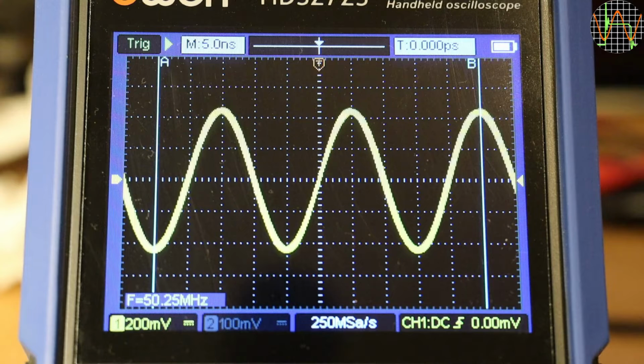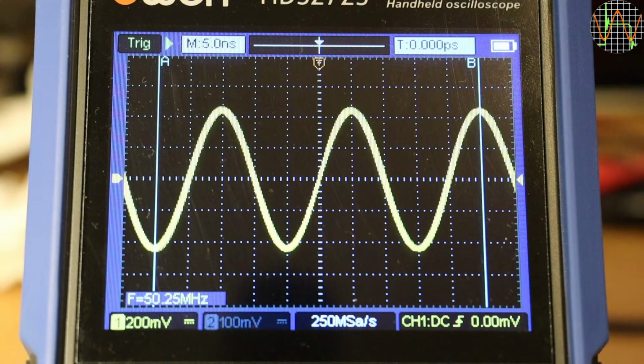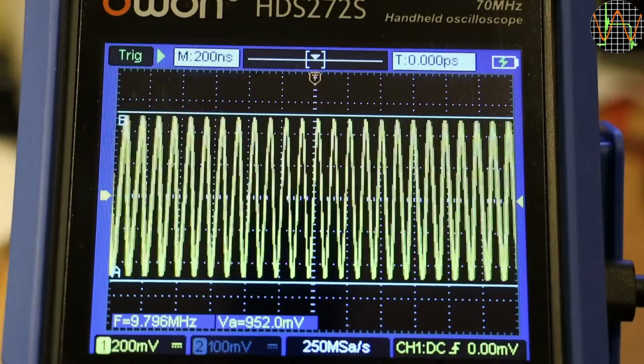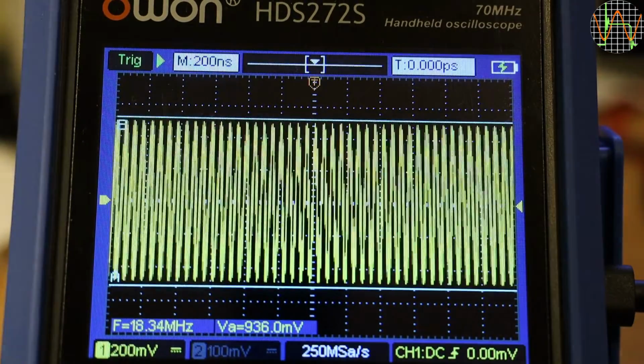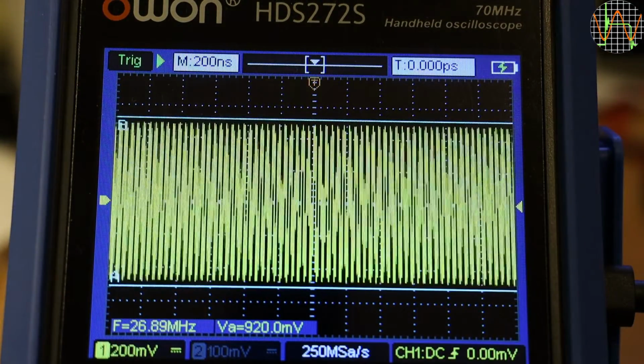The conclusion is that the time base and frequency measurement function of the HDS272S is accurate, but the 70 MHz bandwidth is a pretty hard limit. It kind of works for sine waves, but more complex waveforms with higher harmonics degrade seriously, and 40 MHz is probably the limit where you can still see the difference between a sine signal and one that isn't supposed to be sine. The next question I wanted to know is how linear the horizontal amplifiers are.